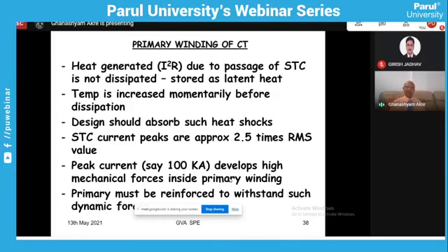Also, the primary should withstand the short circuit dynamic current. When a current like 40,000 amperes is passing for 1 or 3 seconds, the turns will have mechanical forces developed across them, and that can damage the transformer. Generally, the peak current, which is responsible for developing the mechanical forces, is 2.5 times its RMS.